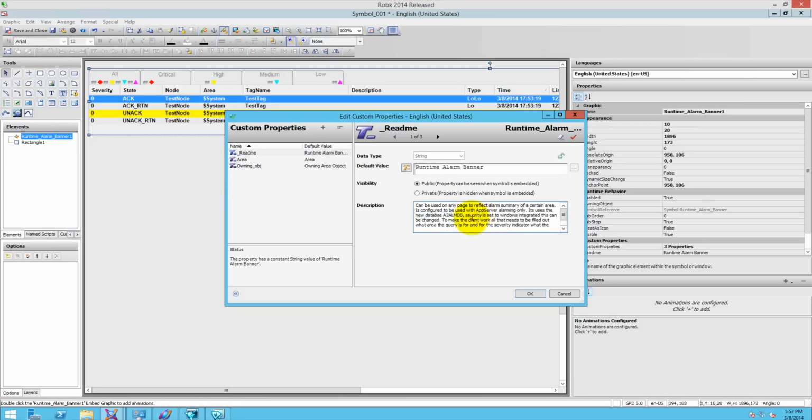One thing, I did a little README in here where you can say what that is to be used with. It's to be used with App Server, preferably, and it uses the new alarm database A2ALMDB. So when you install 2014, you're most likely going to have a database called A2ALMDB, and the security is set to Windows Integrated. So basically, it doesn't need any security options. Also, the time zone is set up to be automatically propagated from the terminal server or the current client. So time zones shouldn't be an issue either.